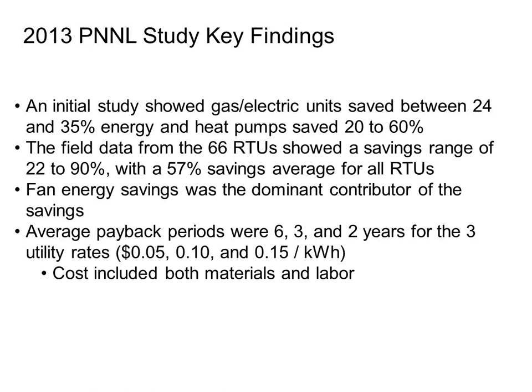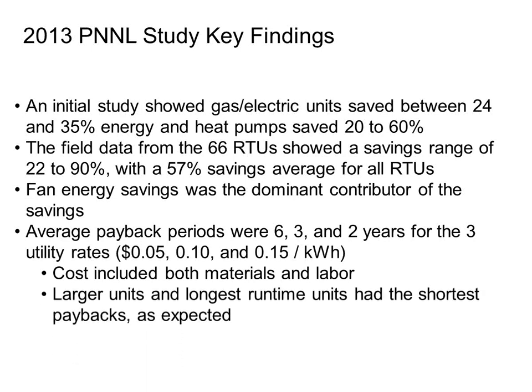The payback costs include both the equipment costs, so dampers, VFDs, sensors, control widgets, etc., and the labor to install those things. These are all retrofits in this particular study. Not only the ones with the higher utility costs having good paybacks, but larger rooftops have shorter paybacks than smaller rooftops, right?